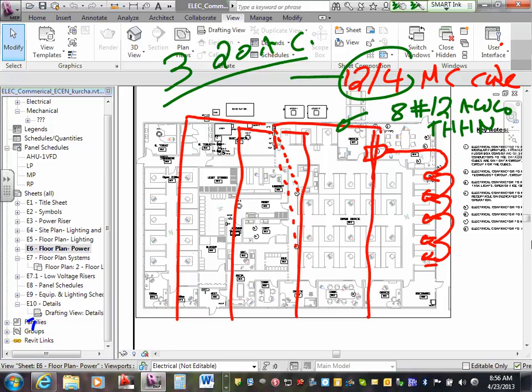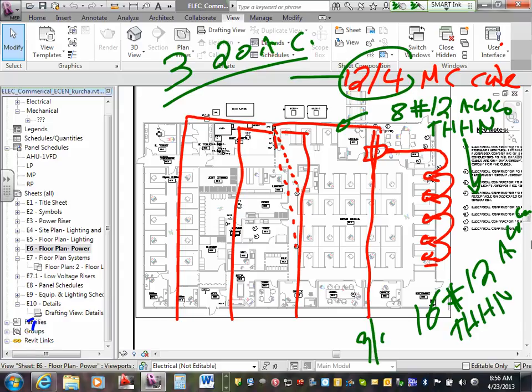So please, when you guys do your layout, I'm looking for EMT conduits, 3/4 inch, with square boxes in the ceiling, grouped together. And you can load them up to, like I said, the assembly that we have been using, which is 8#12. You can use an 8#12 assembly. If you're going to use a non-multi-wire branch circuit, you can still pull. Remember, the code says you can put 16 number 12 AWG THHN in a 3/4 of an inch. So you still can do it, even if you double them. Any comments, any questions? So Darren, my friend, when you guys build your conduits, please, that's what I'm looking for. Build a conduit, lube them up.